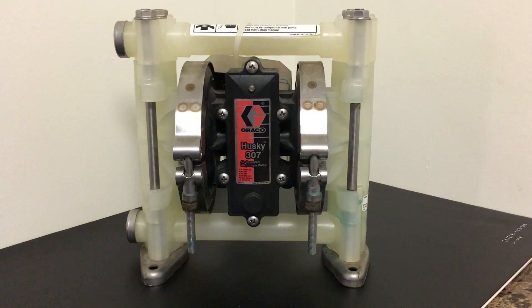First thing you want to do before you even go to the pump and start tearing it apart: look at the lines coming into it, the air pressure, the inlets. Check to make sure everything is working properly. Are you getting air pressure? Is the air pressure regulator working properly? Are the lines clogged, are they dirty? Check the check valve, make sure it's working properly. Don't take the pump apart and then see, oh, something was clogged, something wasn't working properly.